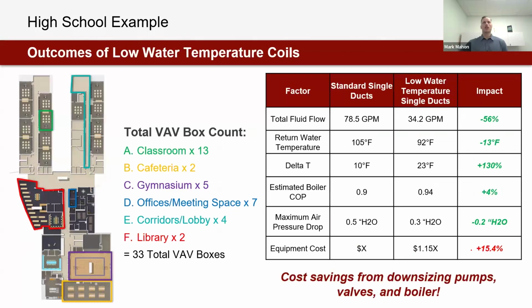Summarizing all these zones together, there actually are 13 classrooms we can see in this little render. There's one cafeteria, but it has 2 VAV boxes. Once again, our gym, which we would do as an air handler, but in the scope of my conversation, I did it with 5 single ducts, which is goofy, but gives me more data to look at. Offices and meeting spaces, we have 2 little offices zoned together, 14 total offices for 7 VAV boxes.